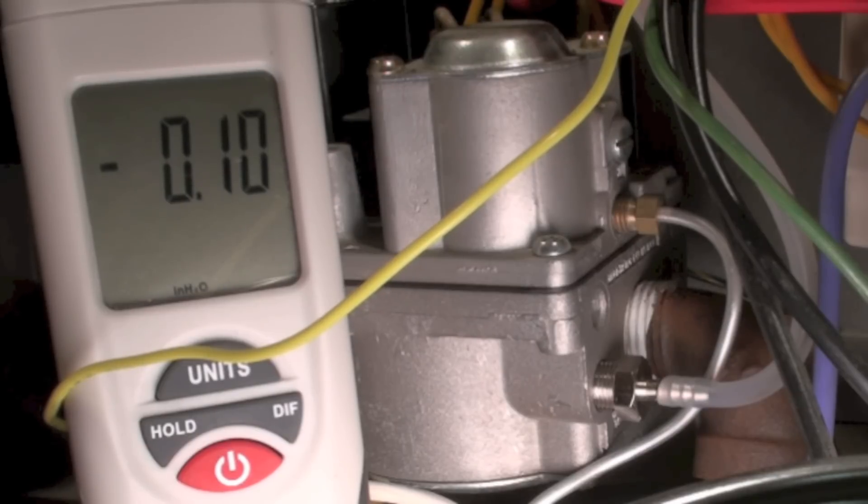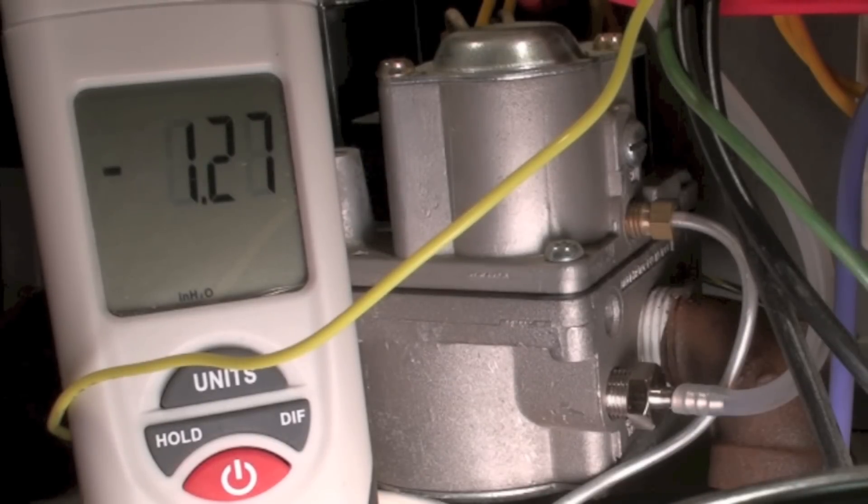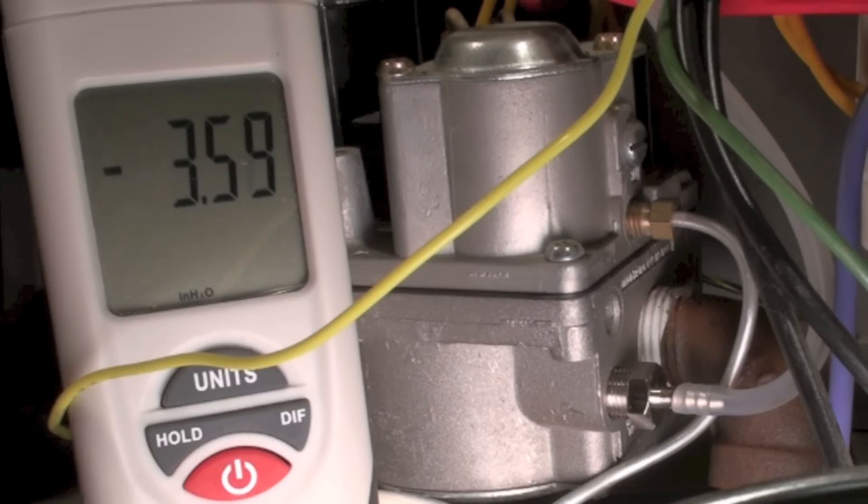I'll talk more about this a little later, but you see we're already reading one-tenth. Now manifold pressure on this is supposed to be 3.5, so when this thing fires up we'll take a look at it and see what it comes up to. Okay, see we're up to pressure. We're running just a skosh over 3.5.